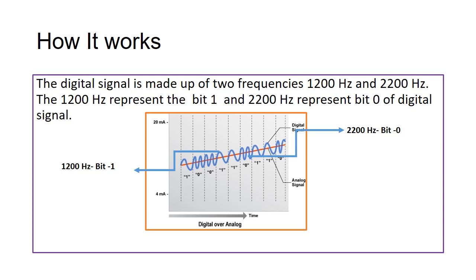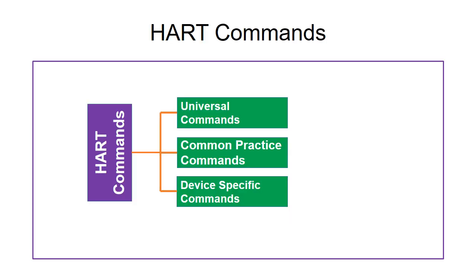HART commands: The HART command set can be classified into three classes — universal commands, common practice commands, and device specific commands. Universal commands must be recognized by all HART enabled devices and are used to access field devices and to read process data.